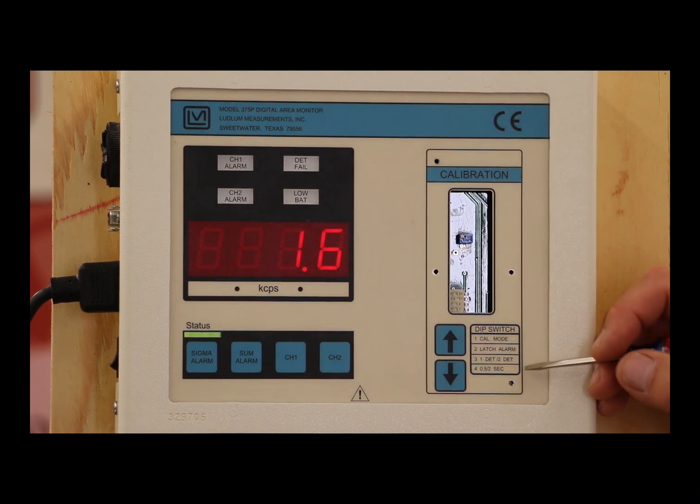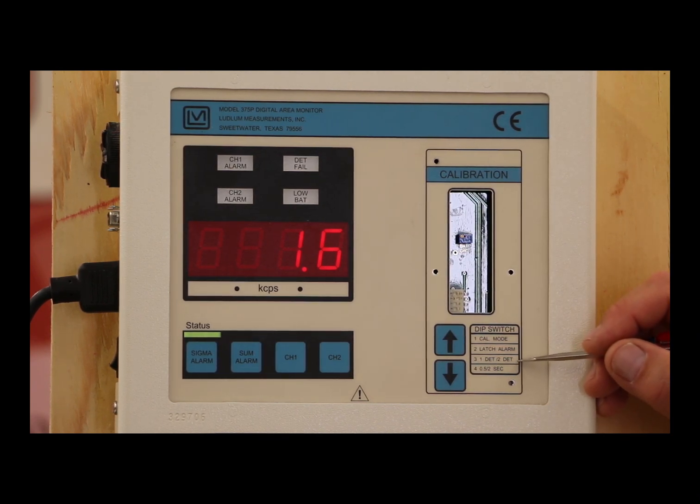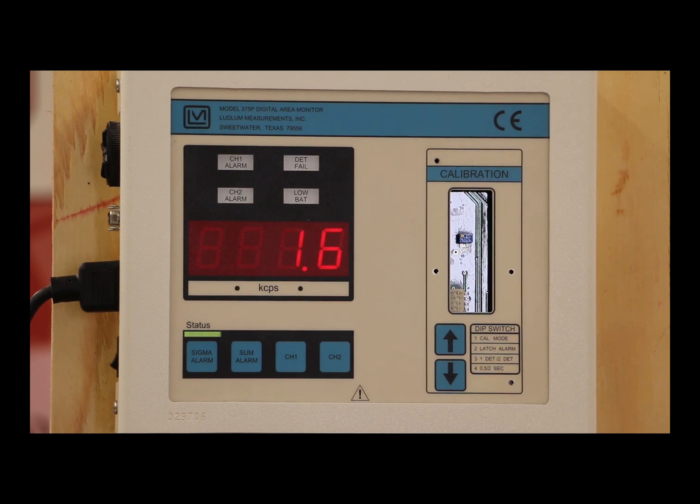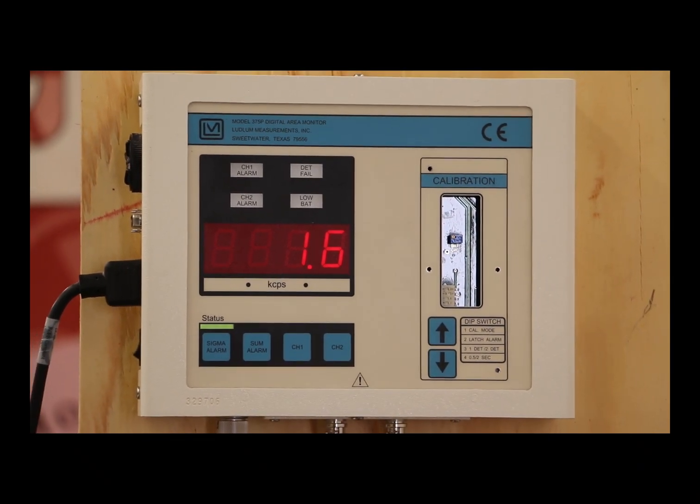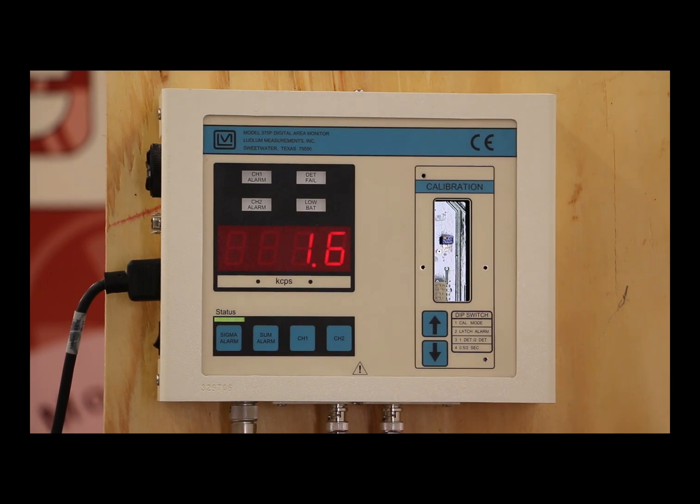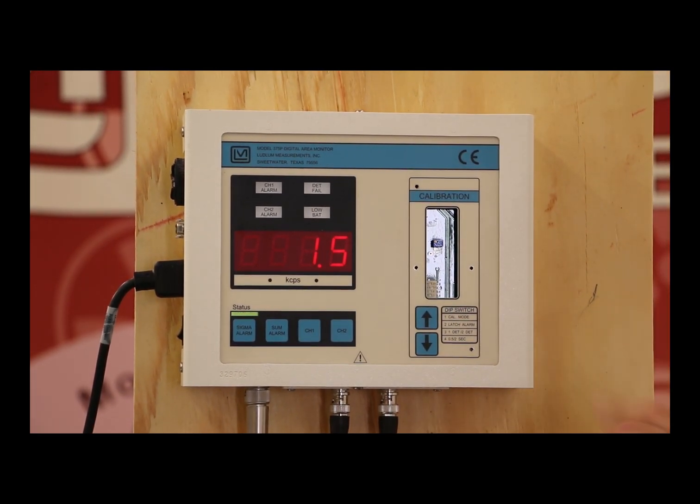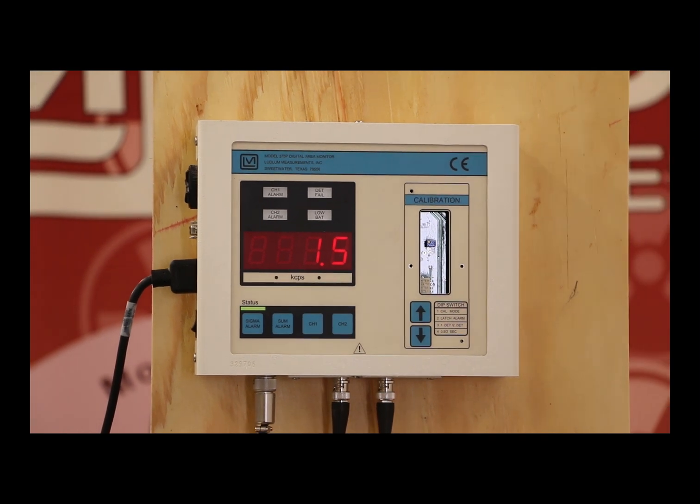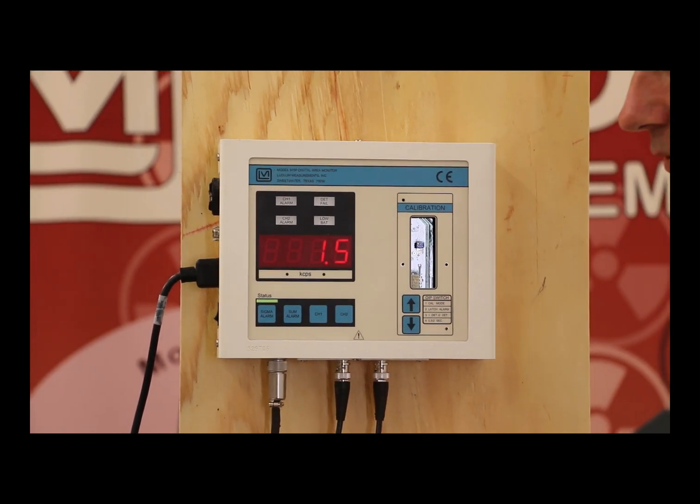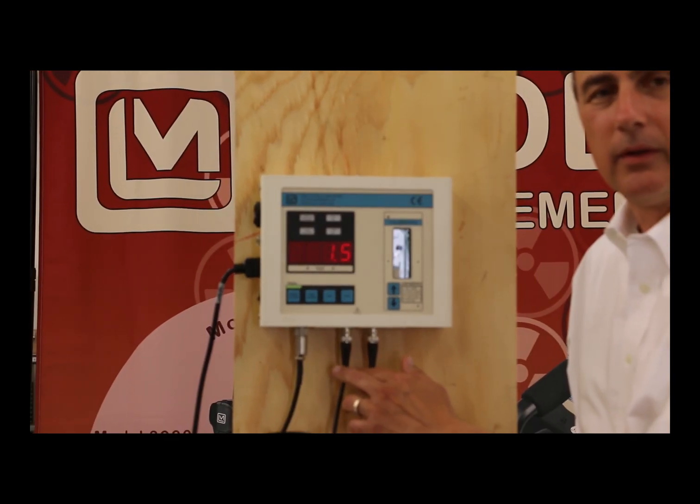The third one down is detectors one and two. What this means is that normally you have two detectors that are operating, feeding into the monitor, but you can have situations where you have a damaged detector or maybe you just have one detector for whatever reason. It can operate with one detector only. When you do that, if you have that situation though, I must tell you that you need to bring the cabling in from that detector into channel one because it expects to see one detector from channel one.